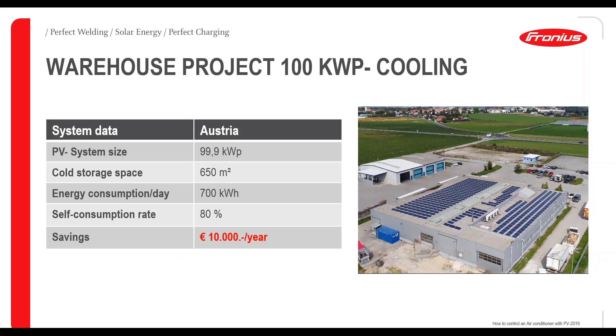Another project is a commercial cooling application — a facility with a 99.9 kWp PV system and a cold storage space of 650 square meters. The energy consumption per day is around 700 kWh for cooling the building and the goods within it. The warehouse achieves a self-consumption rate of about 80% because warehouse cooling runs all day, so PV surplus energy is used to operate the air conditioning of the warehouse. This results in savings of around 10,000 euros per year — a relatively high saving from building a PV system just to operate the warehouse cooling.